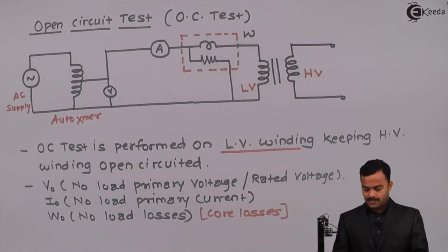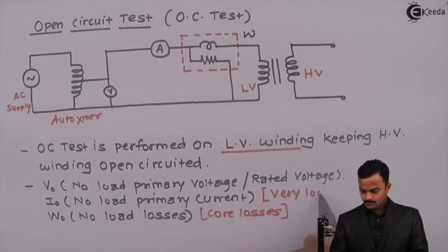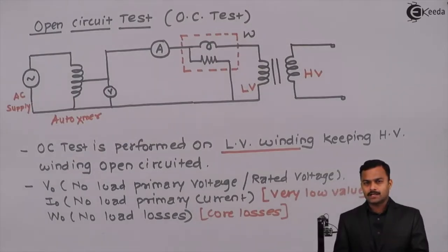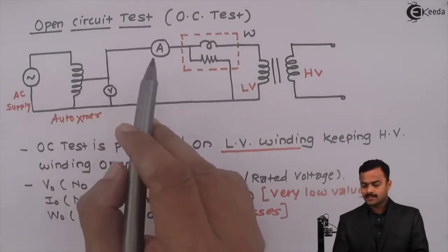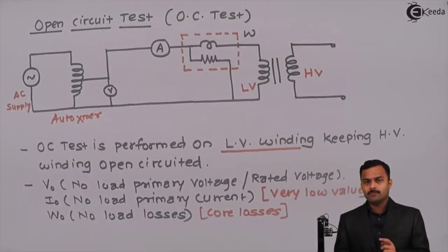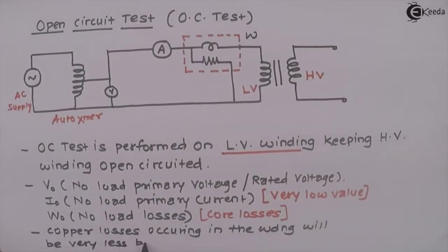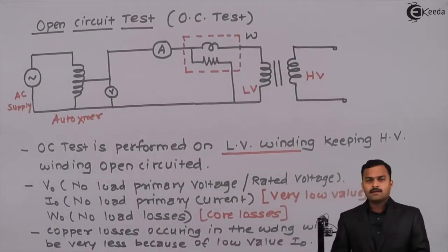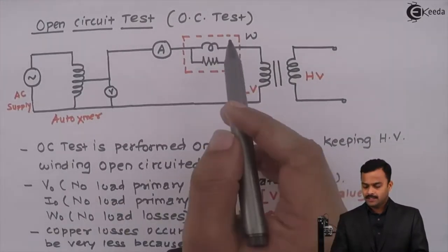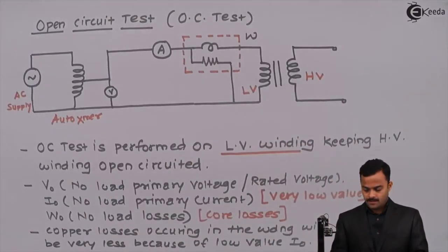I0 is the no-load primary current, which will be very, very low. If the current has a very low value, its square will be even lesser. Hence, copper losses happening in the primary winding will be very less, and whatever power the wattmeter measures will be core losses only.